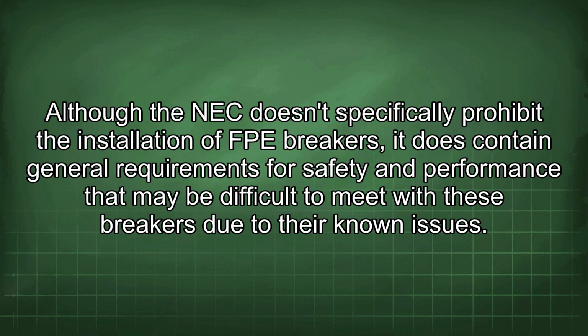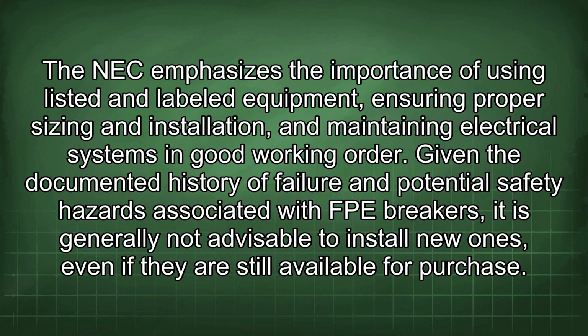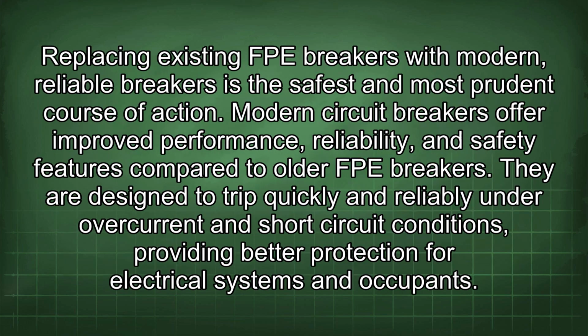Although the NEC doesn't specifically prohibit the installation of FPE breakers, it does contain general requirements for safety and performance that may be difficult to meet with these breakers due to their known issues. The NEC emphasizes the importance of using listed and labeled equipment, ensuring proper sizing and installation, and maintaining electrical systems in good working order. Given the documented history of failure and potential safety hazards associated with FPE breakers, it is generally not advisable to install new ones, even if they are still available for purchase. Replacing existing FPE breakers with modern, reliable breakers is the safest and most prudent course of action.